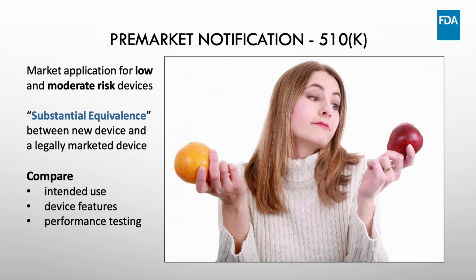The 510(k) is a comparison type of submission in which FDA determines whether a new device is substantially equivalent to a predicate device, which is a legally marketed class 1 or 2 device. In this comparison, FDA examines three main aspects: the intended use, the device characteristics or features, and, as necessary, the results of the performance testing.